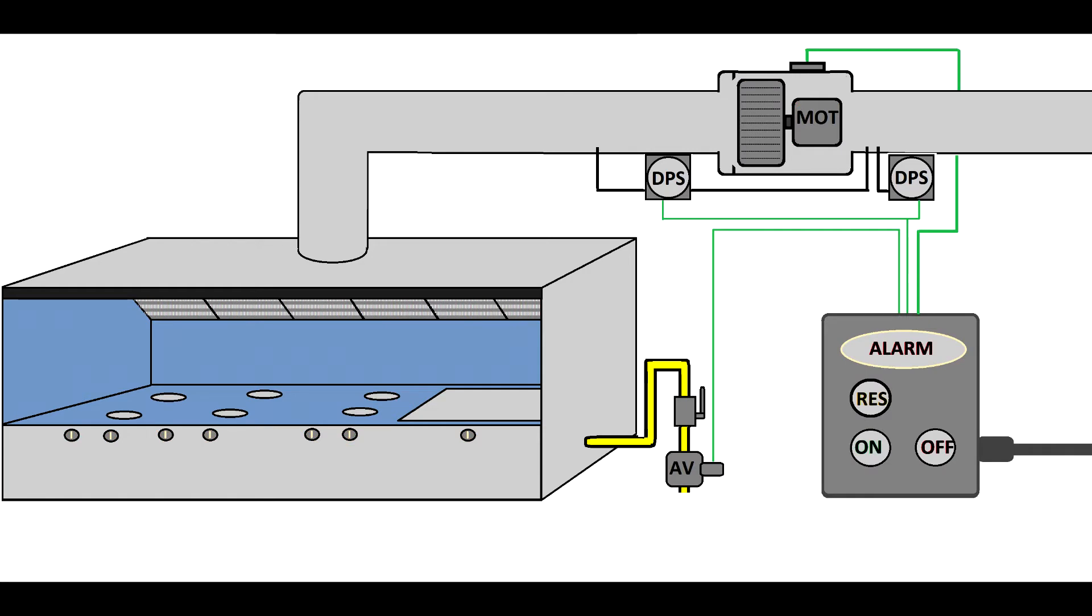Let's see how things work. On this control box, when you press the switch on, first the fan starts turning. When the fan reaches the appropriate speed, it will create a pressure difference before and after the fan. The differential pressure switches will sense that difference and then enable the automatic gas valve.